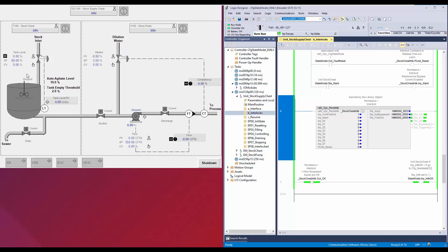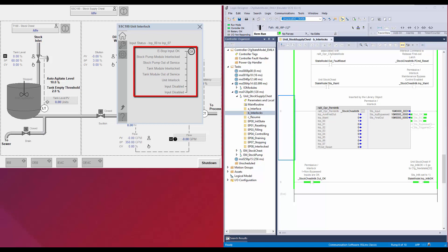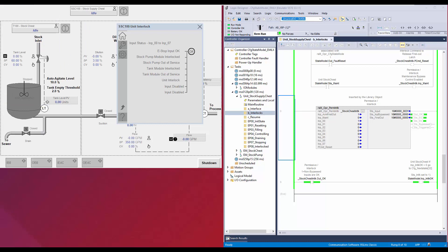I will open the faceplate. There are two faceplate options — the navigation object can be configured to open a quick faceplate or a full faceplate. When using 8 or less inputs, the quick faceplate is suitable. When using more than 8 inputs, the full faceplate can be used. You can see this is a quick faceplate as only 8 input statuses are shown. If needed, the user can also launch the full faceplate from this button. The difference is only the additional pages to display all 32 inputs. Back to the quick faceplate.